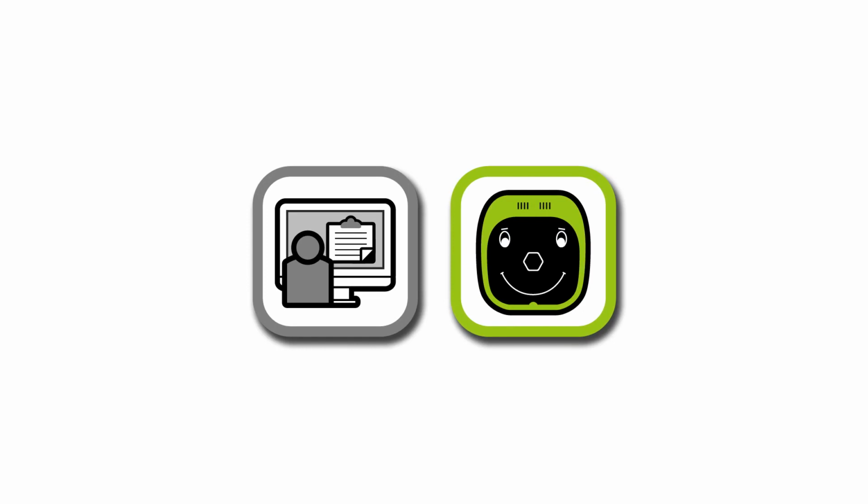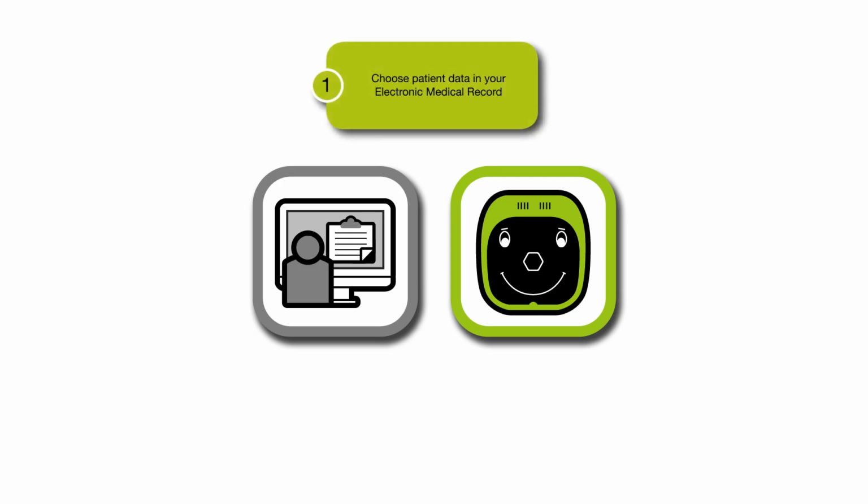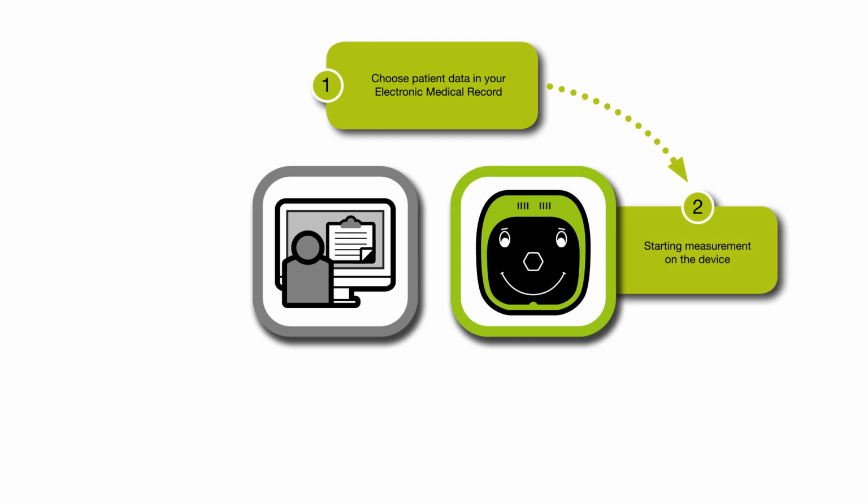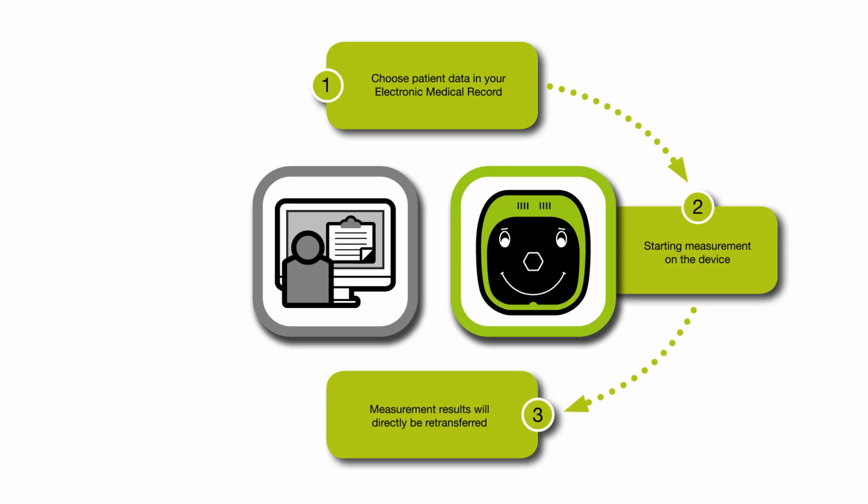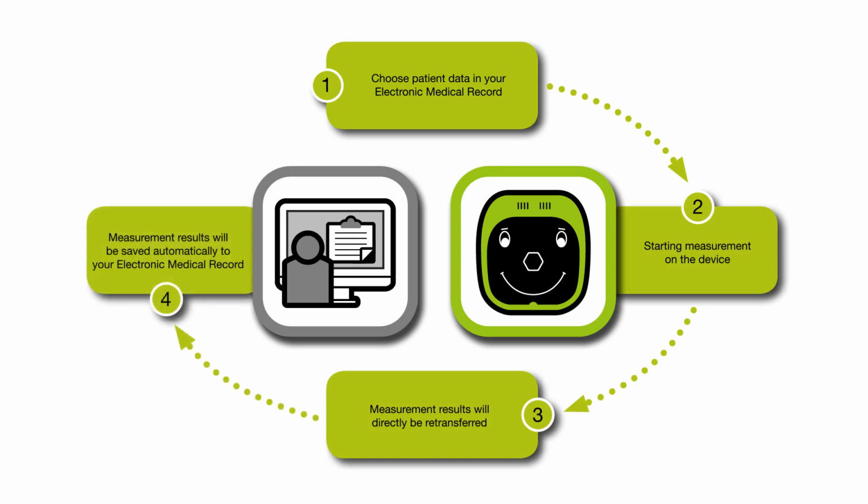As an alternative to the manual entry of the patient data, the plusoptiX A12C can also be connected to your electronic medical record for CSV data exchange and measurement report printing. In this case, you simply choose patient data in your electronic medical record and transfer it to the plusoptiX device. After starting the measurement on the plusoptiX device, all measurement results will directly be retransferred and finally saved automatically to your electronic medical record. For further information concerning the connection to your electronic medical record, please have a look at our homepage under Support.